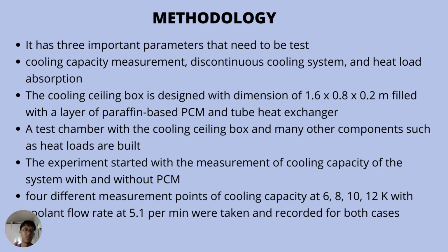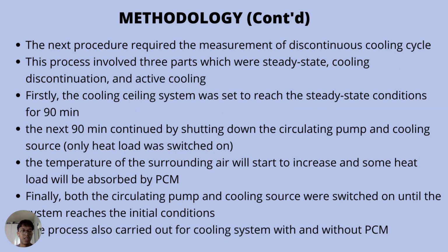For the cooling capacity measurement, there are four different measurement points that were taken for the cooling capacity at 6, 8, 10, and also 12 Kelvin with a coolant flow rate of 5.1 per minute for both cases. The next procedure required the measurement of discontinuous cooling cycle, which involved three important parts, which were steady state, cooling discontinuation, and also active cooling process.